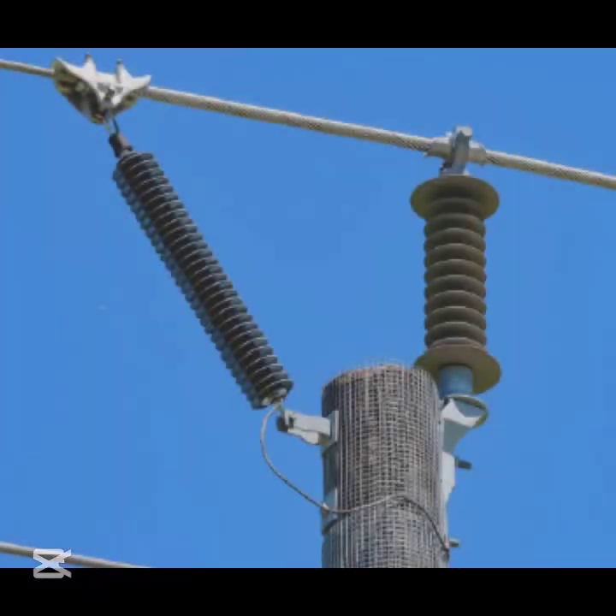Number 6. Line arrestors. Line arrestors are surge arrestors installed directly on transmission lines to protect against overvoltages caused by lightning strikes. They are particularly useful in areas with high lightning activity, or where transmission lines are exposed to direct strikes. Line arrestors help prevent damage to the transmission lines and associated equipment.